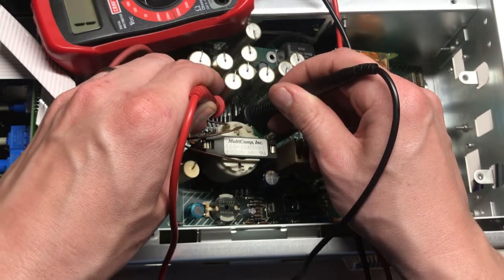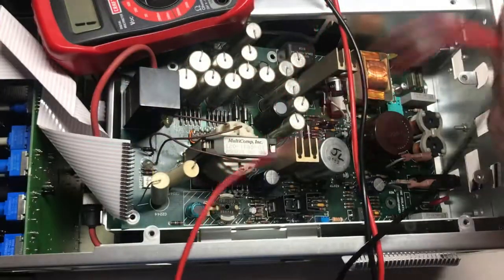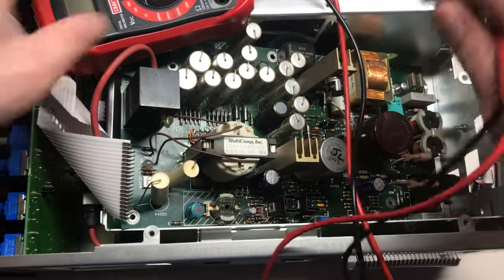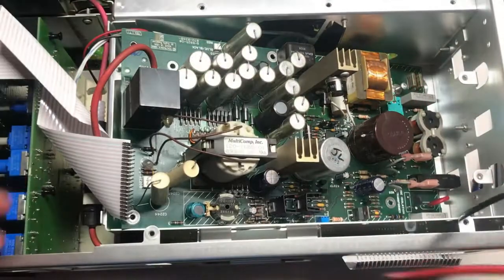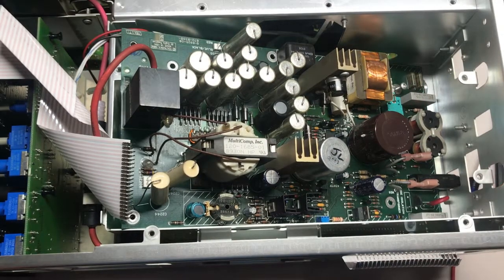No, we're fully open in both directions. So this diode has gone fully open, and that makes perfect sense. With the diode open, obviously the negative 15 volts is impossible for that to be transferred to the main board. So we might as well look at the capacitor while we're at it.